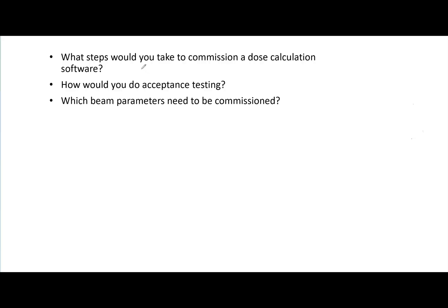What steps would you take to commission a dose calculation software, and how would you do the acceptance testing? Which beam parameters need to be commissioned? This is a very important question for a medical physicist, because we are in charge of the dose calculation algorithms within the TPS and we need to verify that these are working properly and giving us an accurate description of what the dose is going to be.